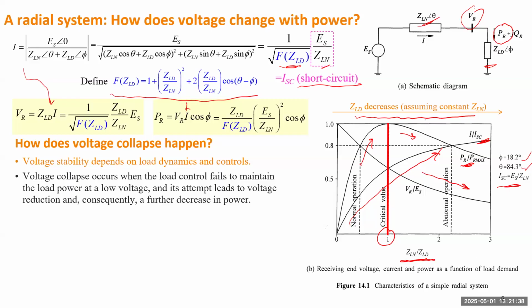Because there are many dynamic load controllers, such as the thermostat load. Remember in the load modeling session, we introduced the heater. If you add a thermostatic controller, then when the voltage decreases, you can increase the time duration of the heater, right, to maintain the room at the same temperature. So for a short time frame, that heater is an impedance load because it is mainly resistance. But over a longer time frame, that heater load can behave like a constant power load.